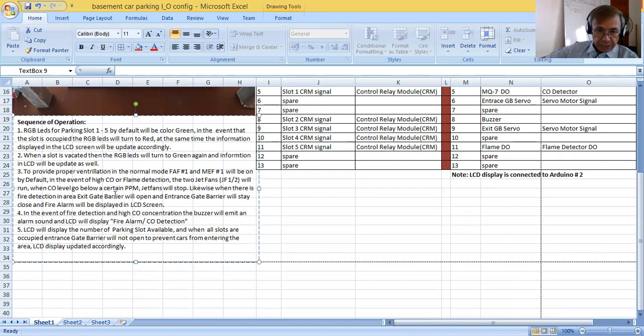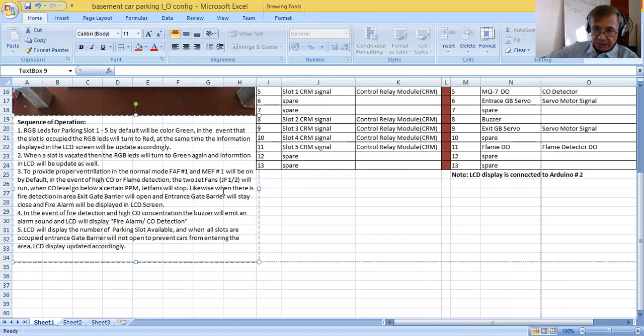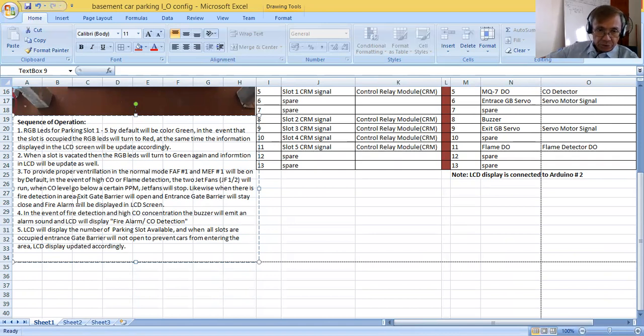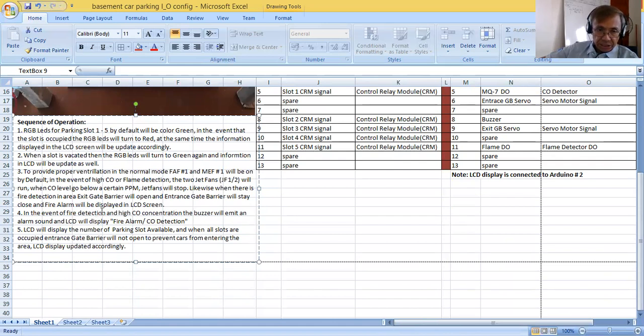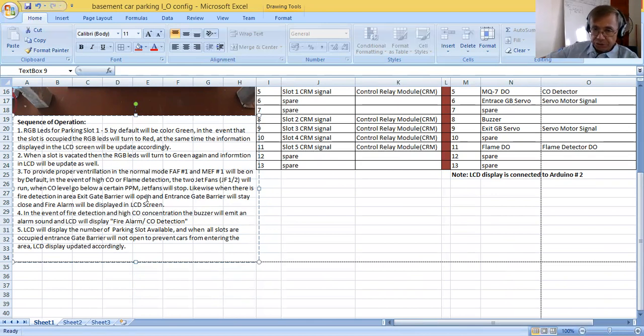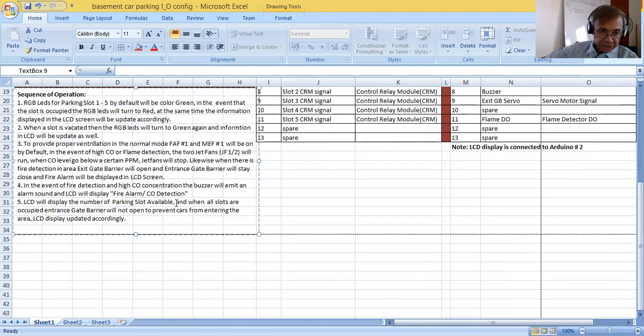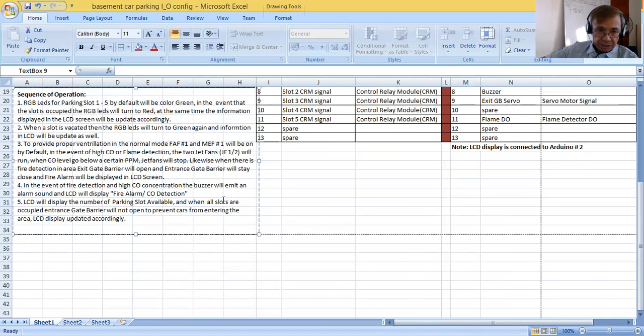In the event of high carbon monoxide or flame detection in the area, the two jet fans JF1 and 2 will run. Then when CO level goes below a certain PPM, jet fans will stop. Likewise, when there is fire detection in the area, exit gate barrier will open and then the entrance gate barrier will stay closed and fire alarm will be displayed in LCD screen.